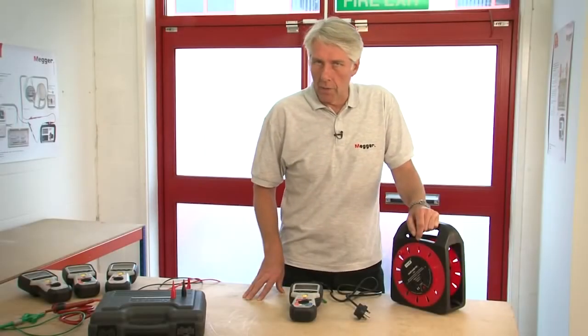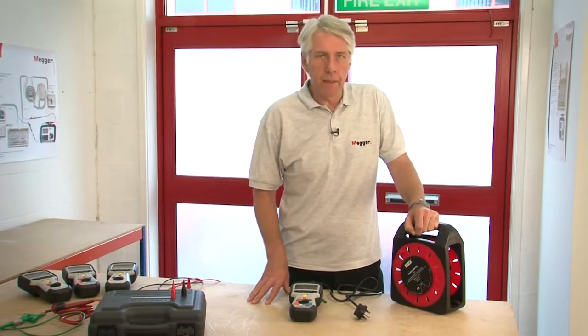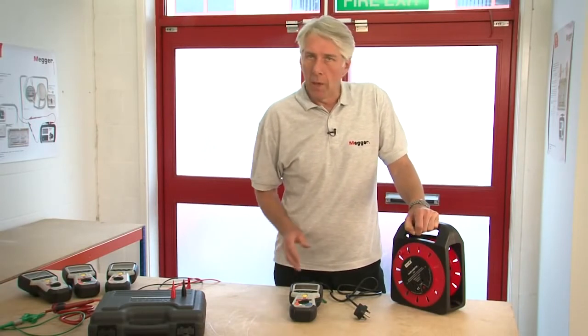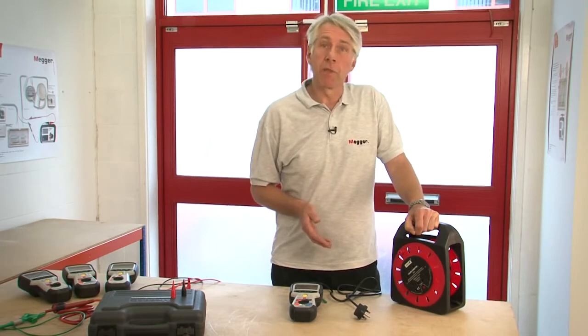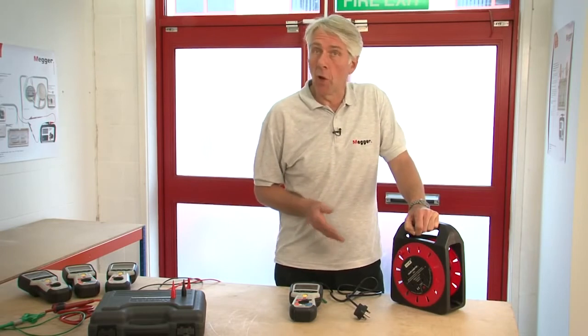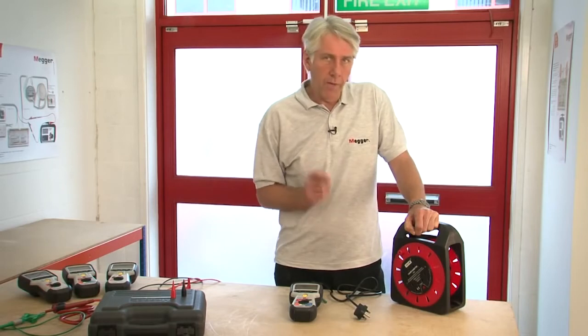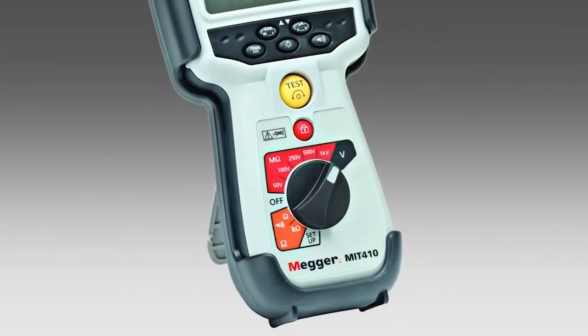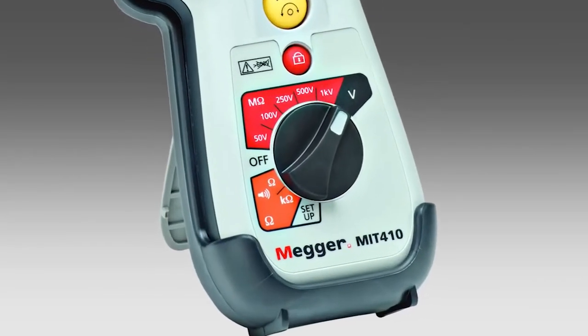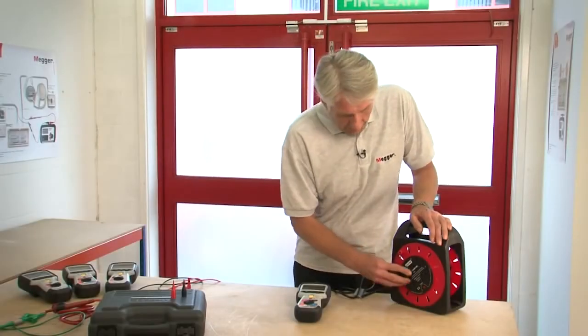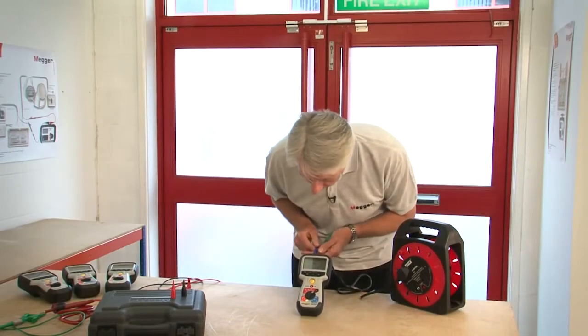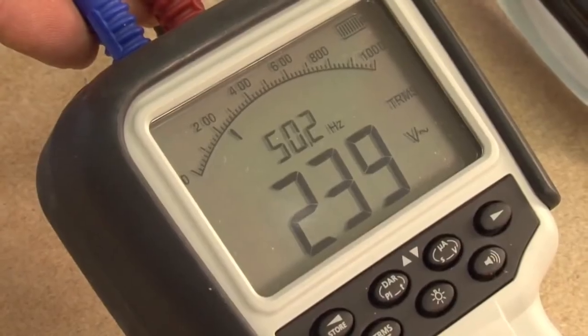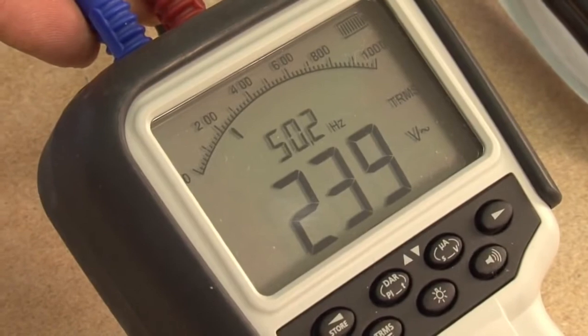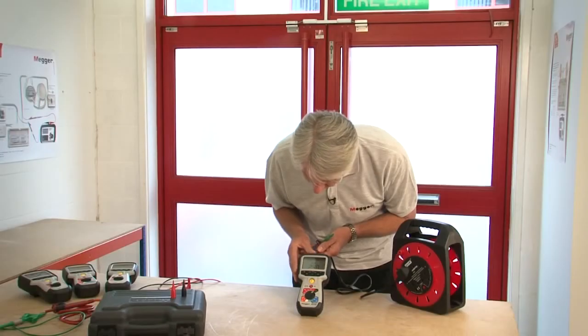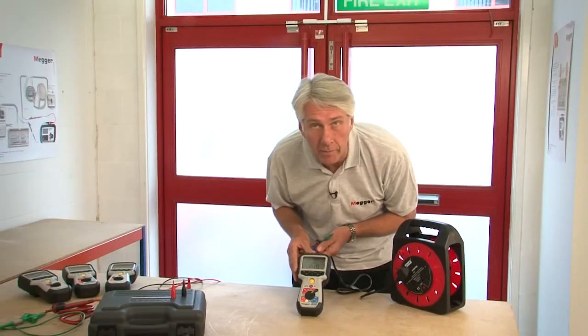What I'm going to show you now is the true RMS AC and DC measurement range. Now, while all MIT400 series instruments are able to display mains level voltage on any range, they do in fact have a selectable dedicated voltage measurement range as well. Now I simply plug into the mains supply, and for the purpose of demonstration, we'll see that we have 239 volts, and it's reassuringly bang on 50 cycles.